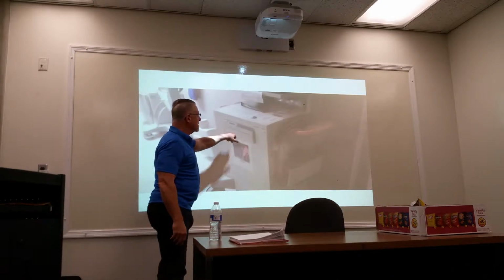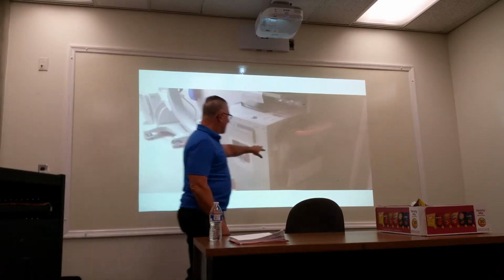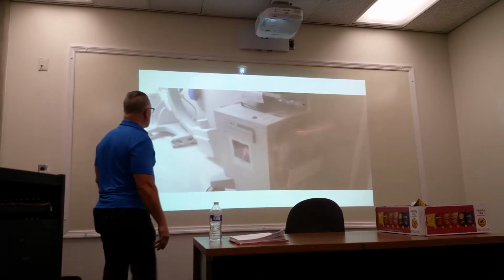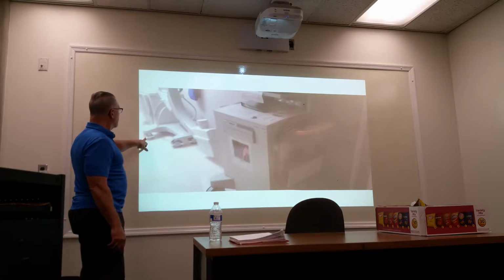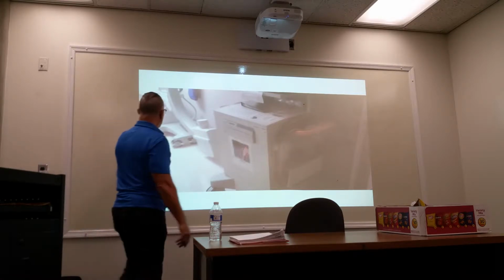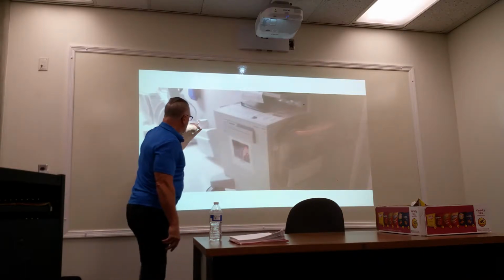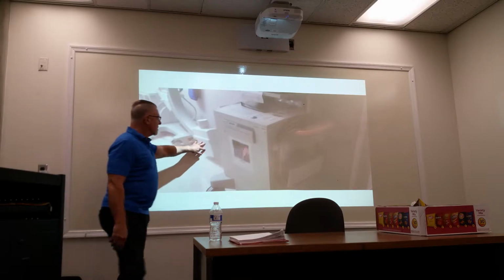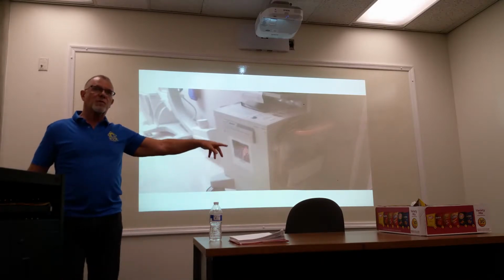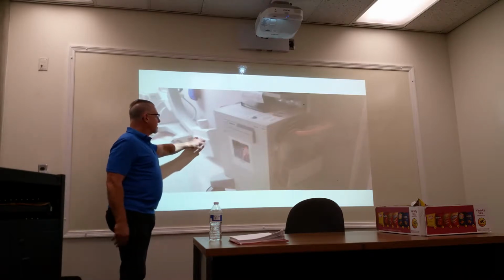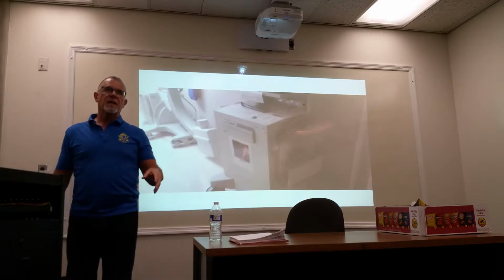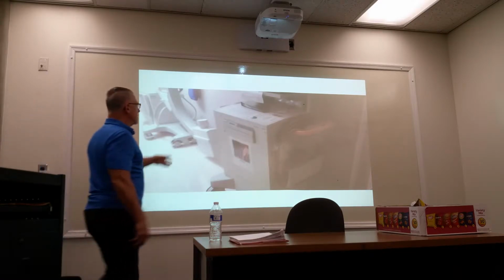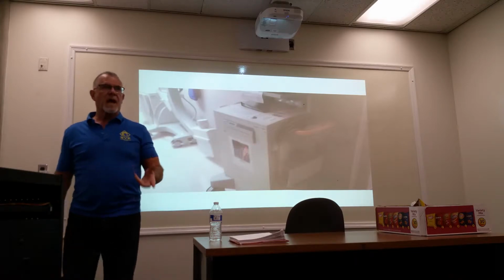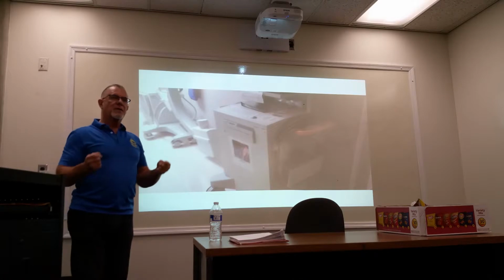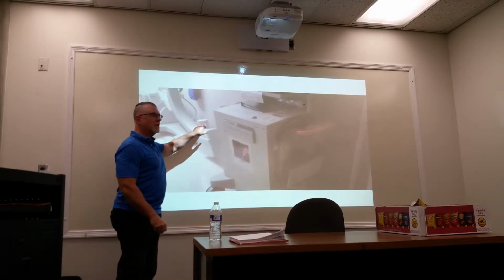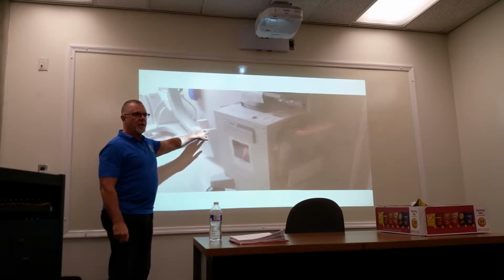So this is a printer color. This is your power cord, someplace to store your pedals. You can see here, I've got a better picture later, but these are the brakes for the wheels. This is your extension cone for the tube. This is an older unit, so it was made to do both surgical cases and normal cases. As you know, the federal regulations allow that for a surgical case, if you need to reduce the distance from the tube to the patient's skin, you are allowed to take that extension cone off. However, once the procedure is done, you pull that out of the room and you store it. Before you walk away from that C-arm, make sure that cone is on.